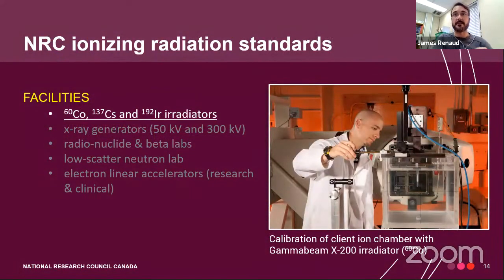So a few of the facilities that we have here at M35. We're equipped with a therapy level irradiator for cobalt-60, we have two industrial / radiation protection level irradiators providing a range of source strengths for cobalt and for cesium, as well as a microSelectron brachytherapy afterloader with high dose rate iridium-192 sources, a Hopewell free air chamber for low dose rate brachytherapy, and a wide variety of low activity radiation sources. The cobalt beams are standardized in terms of exposure, air kerma, and absorbed dose. Typical dose rates range between half a gray to a gray per minute. And these facilities can provide calibrations for therapy class ionization chambers, radiation protection devices, say survey meters, personal dosimeters, etc.